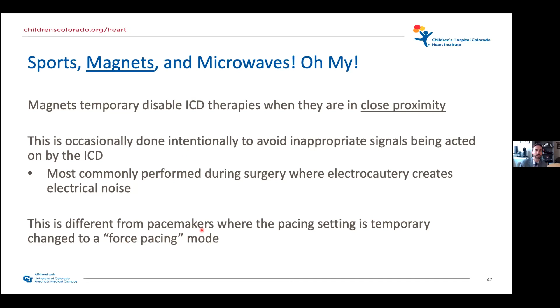Now, why is this done? Well, this is a feature. Frequently, we use magnets to deliberately and intentionally disable therapies during things like surgery, because they use electrocautery, and that creates electrical noise, and we don't want the device to sense that and deliver an inappropriate shock. But this is really different from pacemakers. With a pure pacemaker, a magnet will actually set it to a forced pacing mode. So for somebody who has an ICD but also requires that device for pacing, a magnet acts differently. If you have an ICD, it's a conversation to have with your electrophysiologist about what the effect is on you when a magnet comes close.